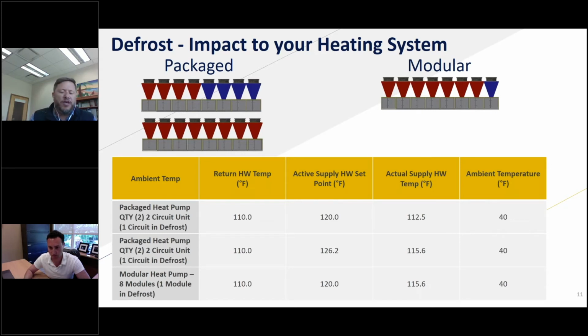That might have unloaders. But if we look at getting into a variable speed environment, sure, that does change the equation a little bit, and that would change what the resultant heat output would be, whether we go into defrost or how we go into defrost. That would have an impact on it. Yep. And as technology evolves and changes, this discussion will evolve and change as that happens.